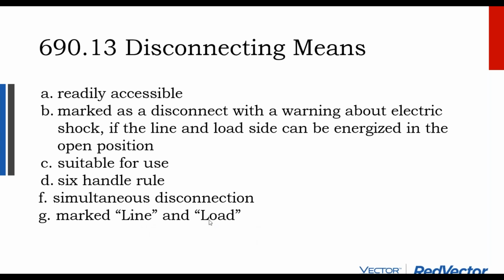And I probably should have put a graphic in at this point, but the number one mistake that installers make with this disconnect switch is that it does matter whether the grid lands at the top of the switch or the bottom of the switch. And the rule is, even if the grid comes up from the ground and the solar array is coming down from the roof, you might think, okay, I'm going to land the solar array at the top of the switch and the utility line at the bottom of the switch. And that's a code violation. The utility, the line, the supply, and it's a little weird because solar is not a load, it's a supply, but the main supply, the grid supply, needs to land at the top of the switch, and solar lands at the bottom of the switch.